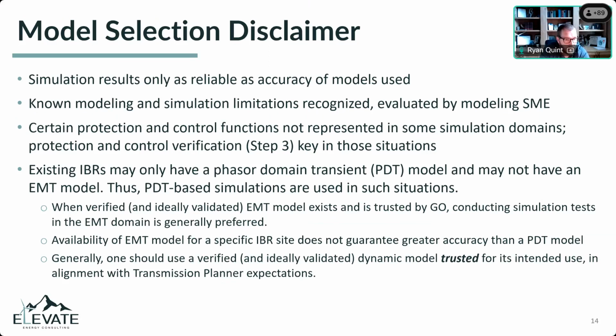We've had a number of cases where the OEM says, yes, we have this protection enabled, it's set at 5 hertz per second, whatever. Okay, we simulate 6 hertz per second in PSCAD and we see no tripping. We go back to the OEM and they say, oh, it's not actually represented in the model. So we can't presume that these models have all these protections in them. We want to check them, but we have to take those models provided by the OEM at face value because they're often black box. We do the best we can.